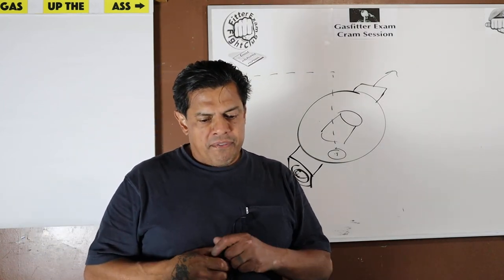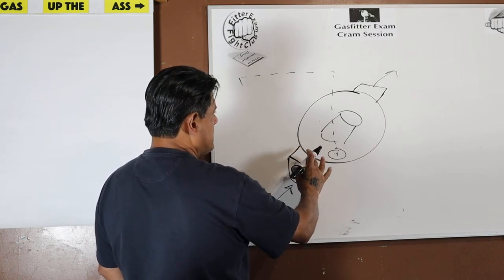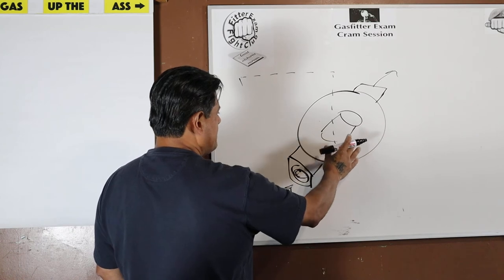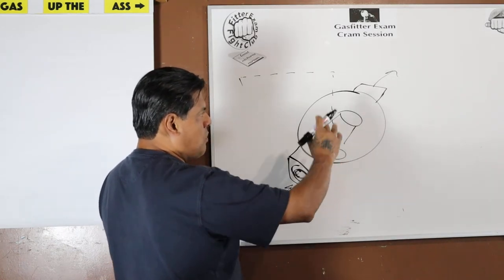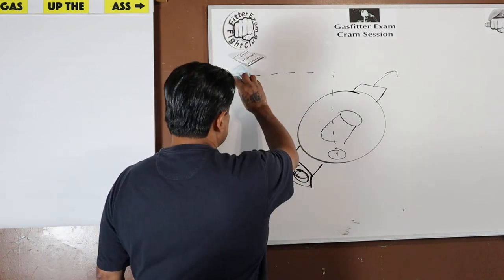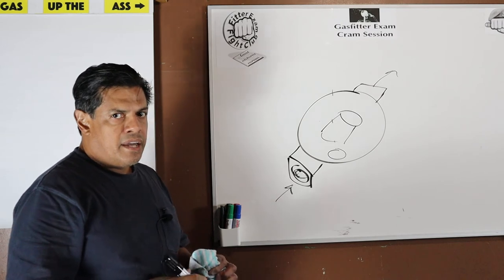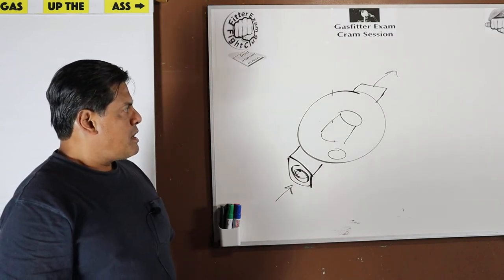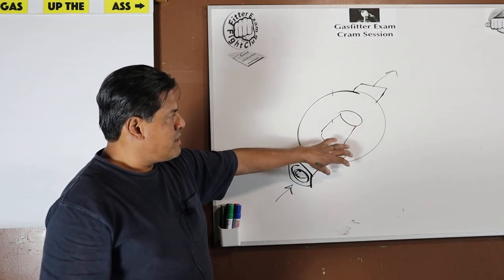But if you have a gas pressure regulator, a regulator that even if gas escapes or is being relieved in some way, there's a device within the regulator, or equipped onto the regulator, so that the amount of gas escaping will always be contained to a certain amount that it will never overwhelm the area that it's in. It'll never cause enough of an explosive mixture. Then we don't even need the vent, because this regulator with its vent limiting device is actually self-regulating. It's going to relieve pressure to allow the regulator to work properly, to avoid creating any hazardous situations. But that alone is also going to be limited or regulated by another device so that we don't need the vent.